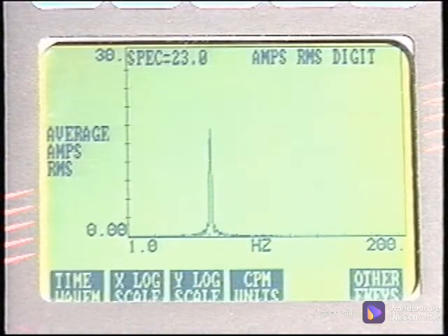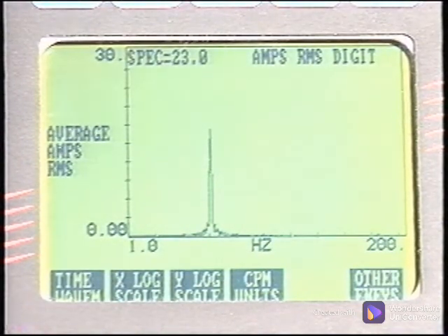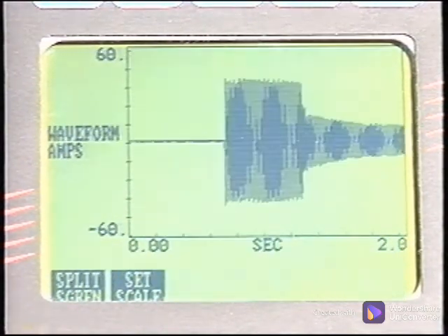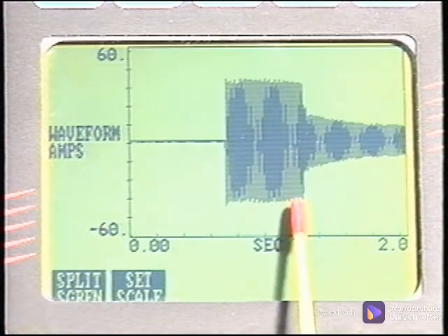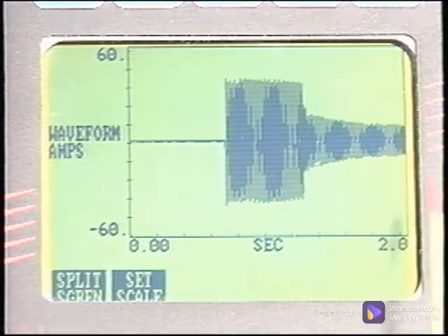machine. The inrush current will trigger the analyzer to capture the data. The waveform data shows the amount of the startup current drawn and the length of time until normal running current is reached. It is not uncommon for the startup current to be 10 times as high as the normal running current. Use these applications of vibration and current measurements to enhance your RBM program, increasing uptime and profitability.